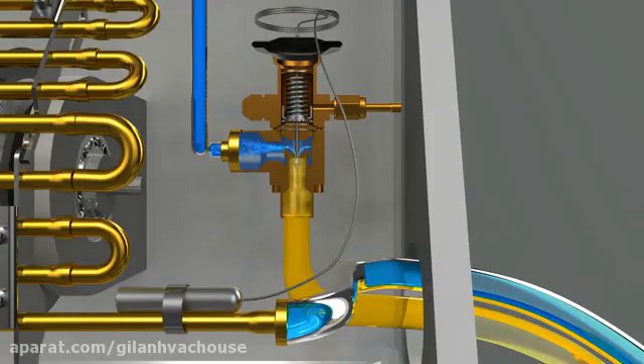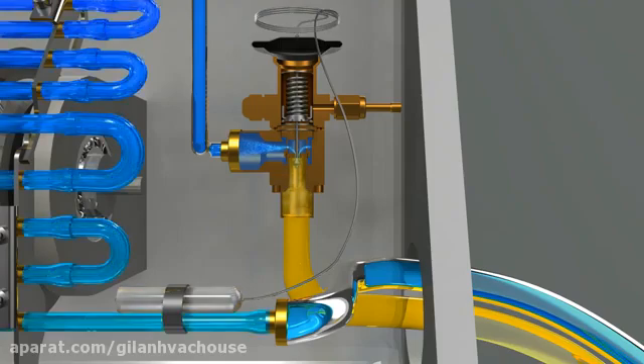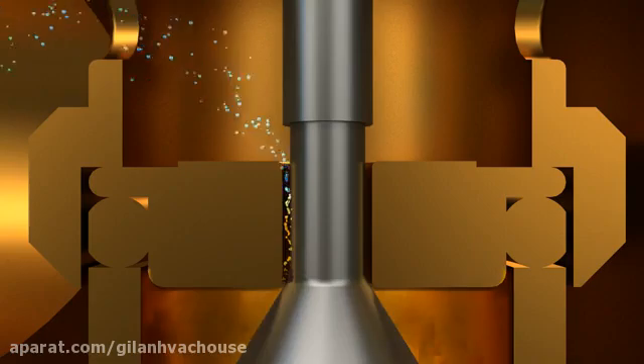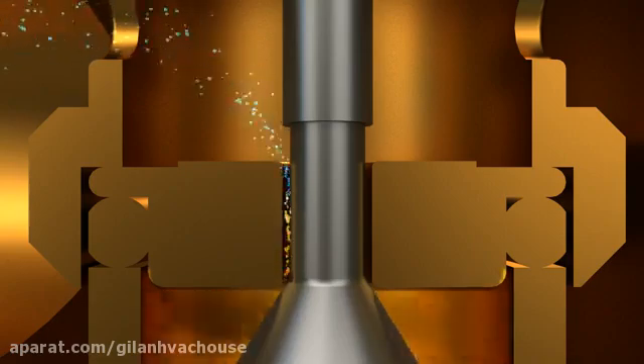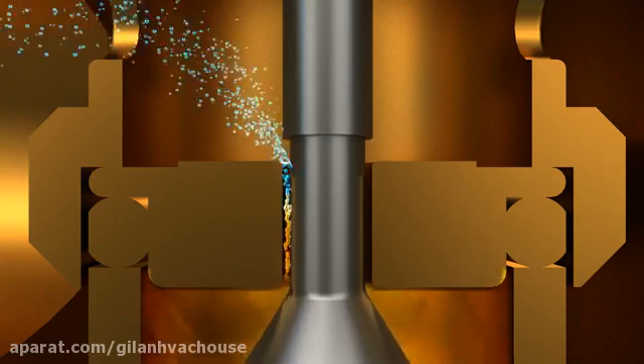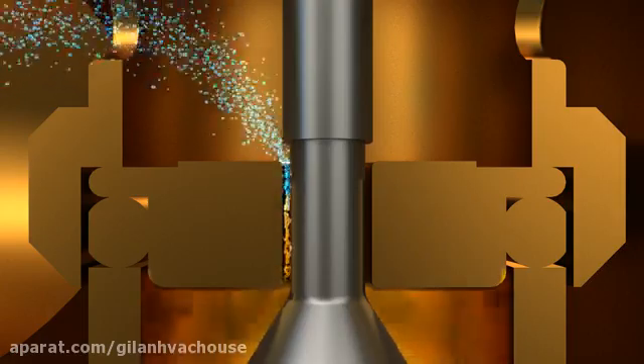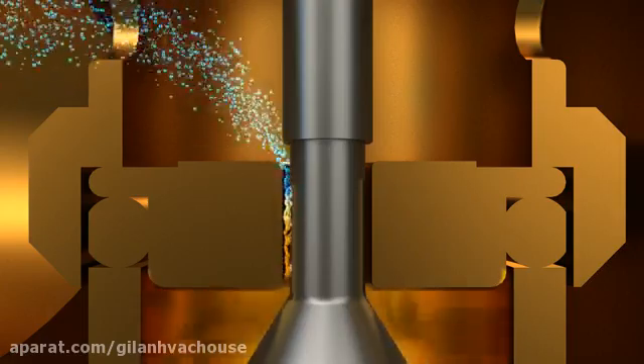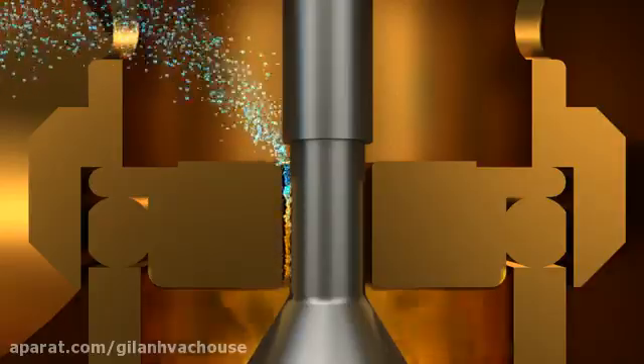The expansion valve is connected to a sensing bulb that detects heat. The sensing bulb is installed on the exit of an evaporator and detects temperature. Inside the bulb is fluid sensitive to temperature changes, and as the temperature at the exit of an evaporator rises, the gas pressure rises, which in turn presses on a spring to send more refrigerant to the evaporator. When the amount of refrigerant going into the evaporator surges, cooling emission surges too.